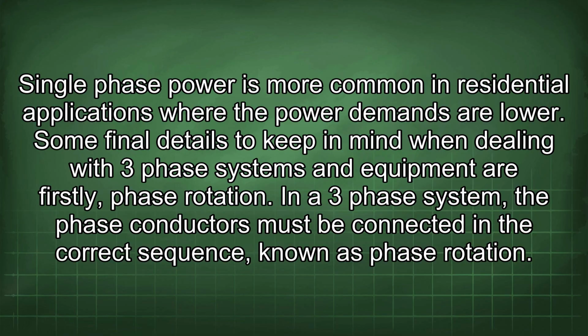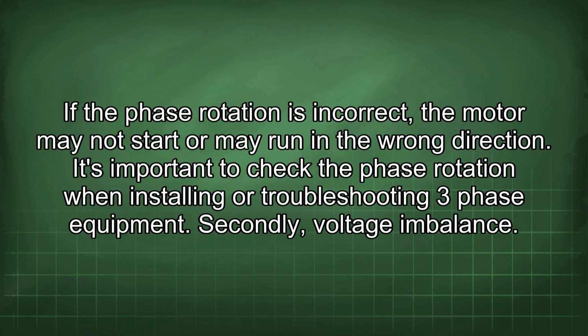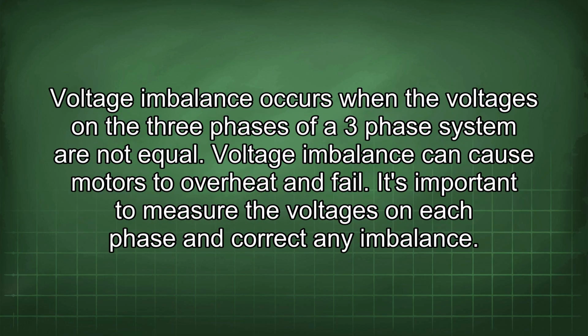Some final details to keep in mind when dealing with three-phase systems and equipment are, firstly, phase rotation. In a three-phase system, the phase conductors must be connected in the correct sequence, known as phase rotation. If the phase rotation is incorrect, the motor may not start or may run in the wrong direction. It's important to check the phase rotation when installing or troubleshooting three-phase equipment. Secondly, voltage imbalance. Voltage imbalance occurs when the voltages on the three phases of a three-phase system are not equal. Voltage imbalance can cause motors to overheat and fail. It's important to measure the voltages on each phase and correct any imbalance.